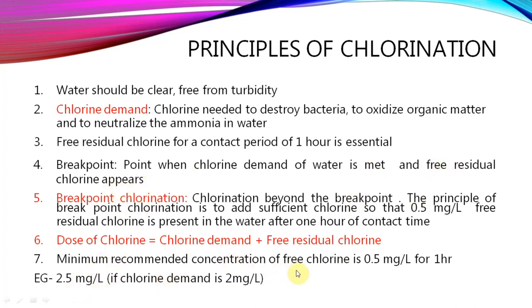The minimum recommended concentration of free residual chlorine is 0.5 milligrams per liter for one hour contact time. For very contaminated water, the breakpoint chlorination may require more chlorine - for example, 2 mg/L or even 5 to 7 mg/L depending on contamination level - and then 0.5 mg/L extra is added so that 0.5 mg/L free residual chlorine remains for the disinfection action. Chlorination can be done using chlorine gas, chloramine, or hypochlorite - commonly chlorine gas is used.